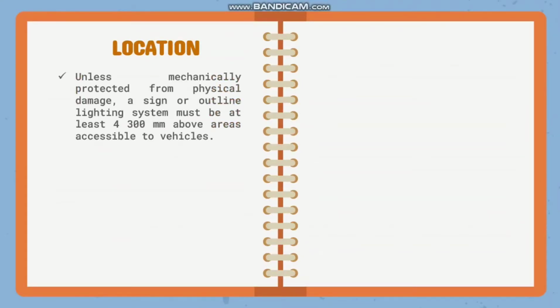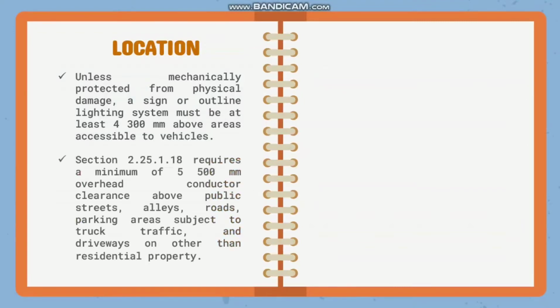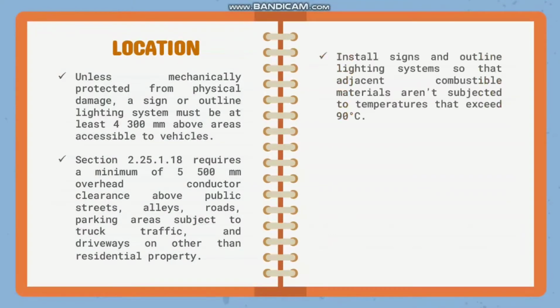Location. Unless mechanically protected from physical damage, a sign or outline lighting system must be at least 4,300 mm above areas accessible to vehicles. Section 2.25.1.18 requires a minimum of 5,500 mm overhead conductor clearance above public streets, alleys, roads, parking areas subject to truck traffic, and driveways on other than residential property.